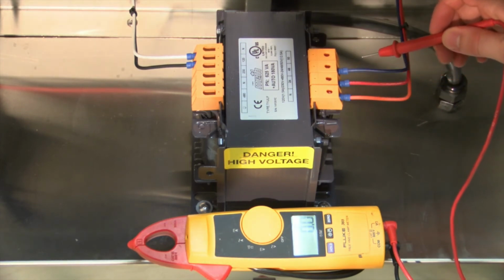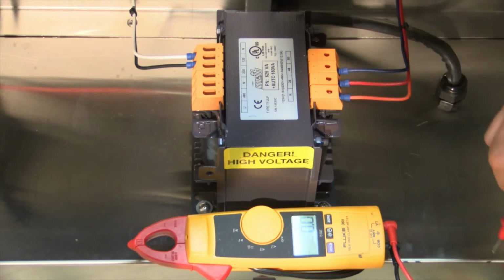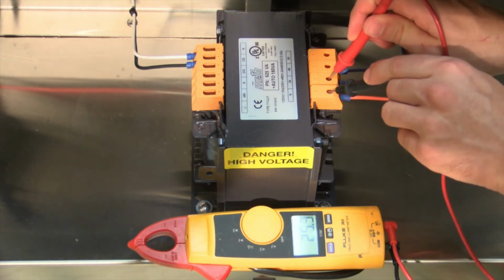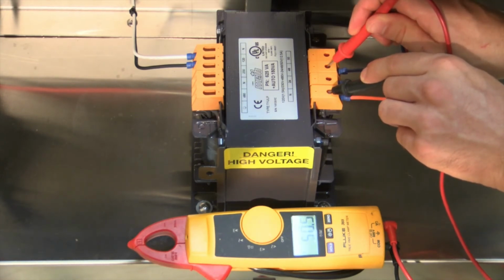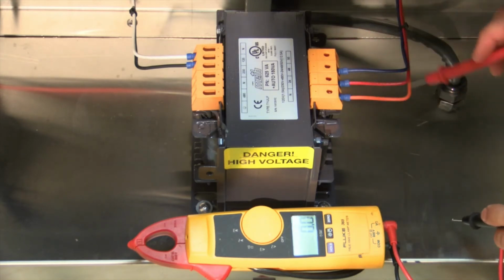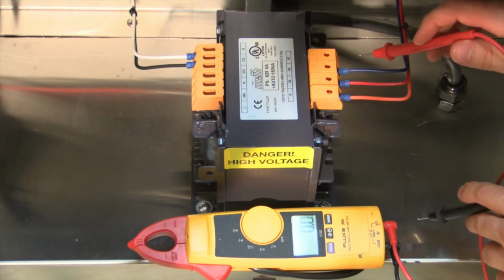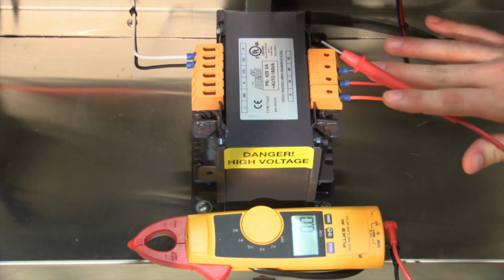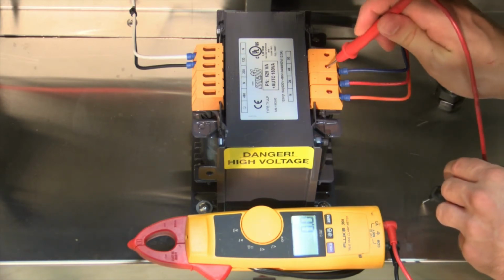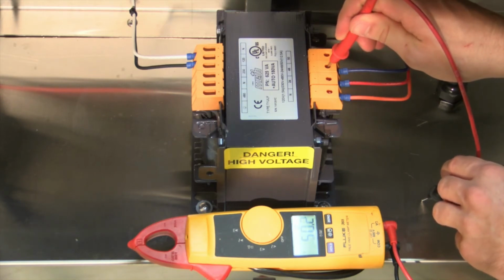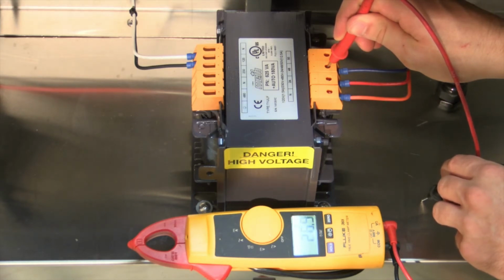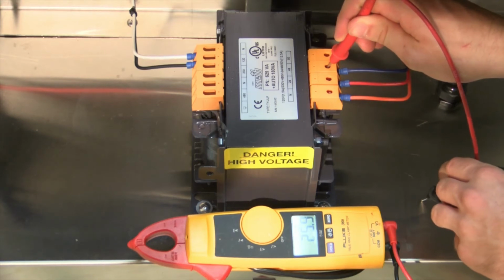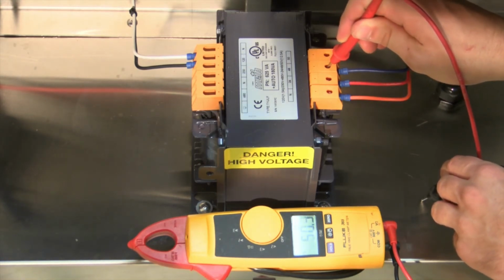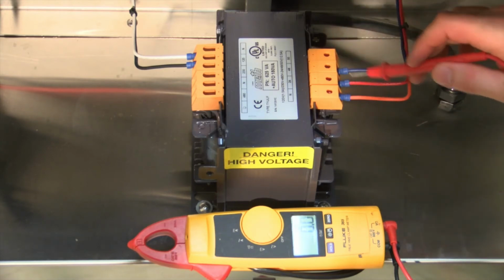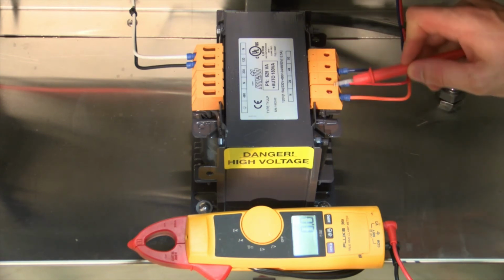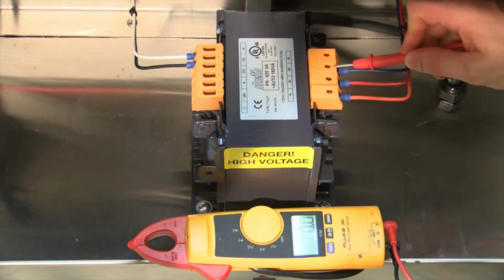On the secondary side of the transformer, you must use the secondary neutral to get an accurate reading. In this case, we'll take a 24 volt reading on the red wire and a 48 volt reading on the blue wire. Taking a reading on the secondary side of the transformer against ground will not give you accurate readings. We'll show you this now when the transformer is drawing. As you can see, when the transformer is drawing, you cannot get an accurate volt reading to ground. When reading the secondary side of the transformer, always use the secondary neutral to take your power readings.